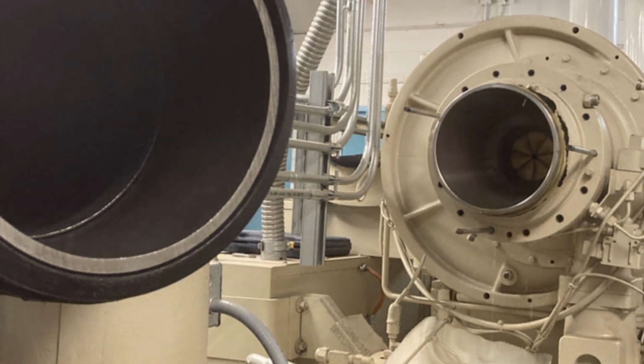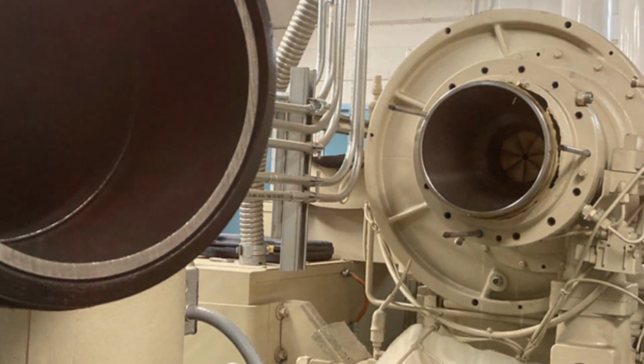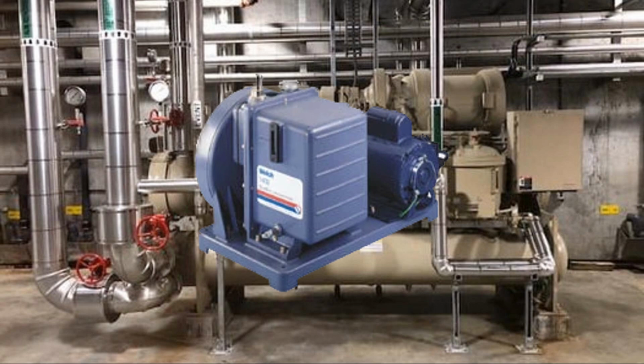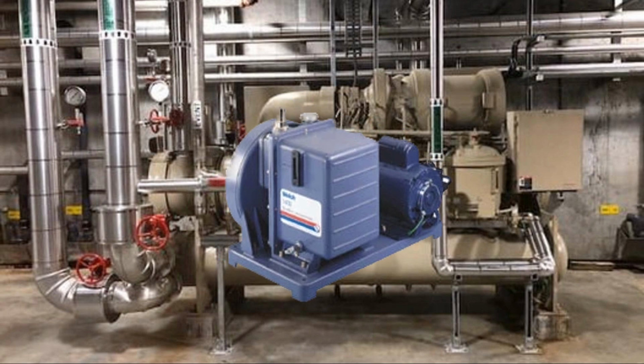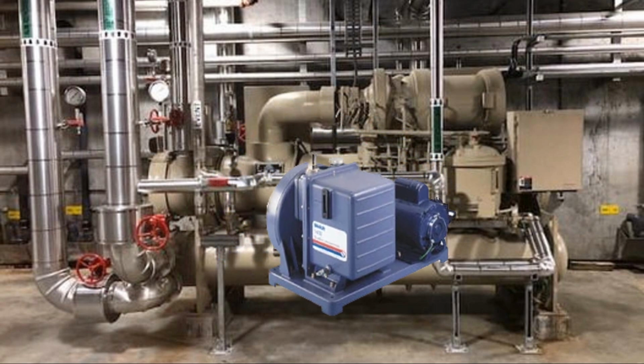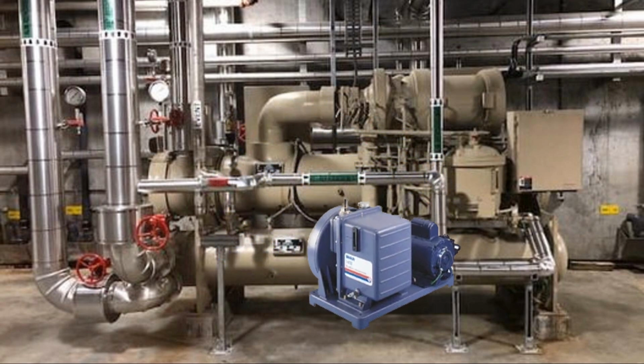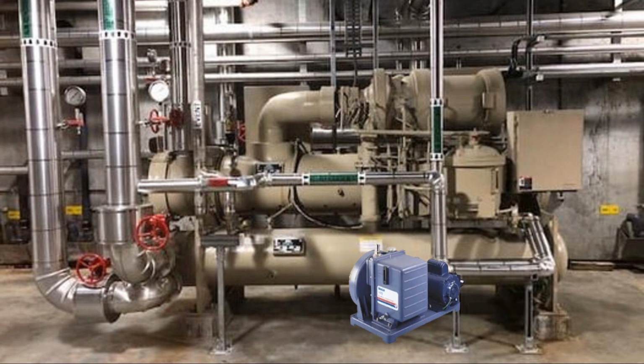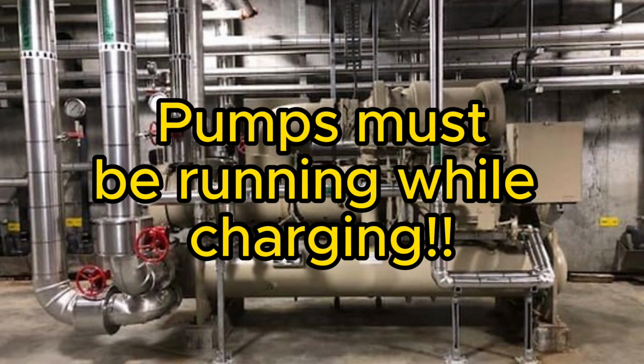After you're done recovering the vapor, make the repairs you need, pressure test the machine, then evacuate the machine, and perform a decay test. I'm usually a little paranoid, so I'll start up the vacuum pump for a little bit longer after I'm done with that to be 100% certain no air was let into the system when I removed my micron gauge. Recharging the machine is the exact opposite of the way you pulled the refrigerant, except for the last step.